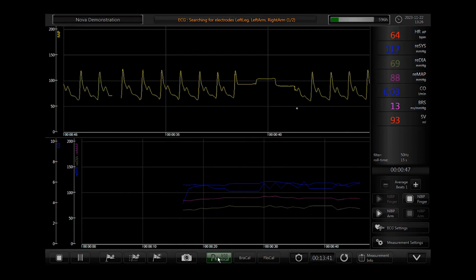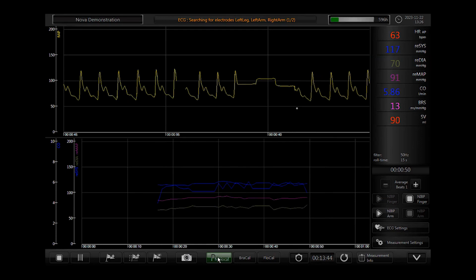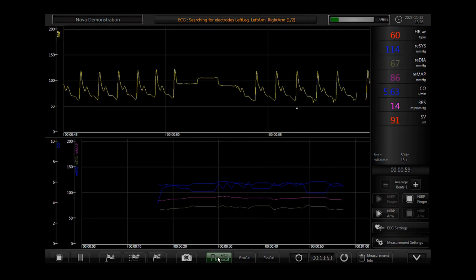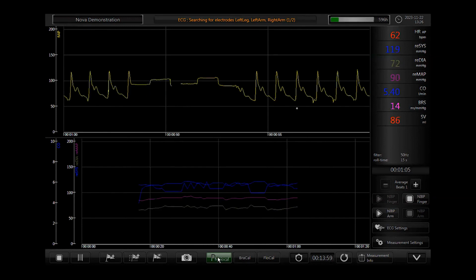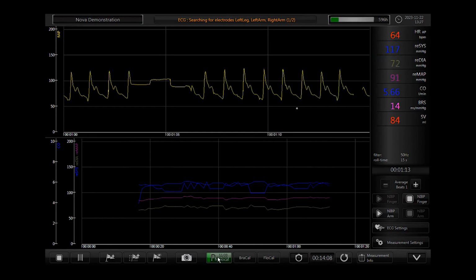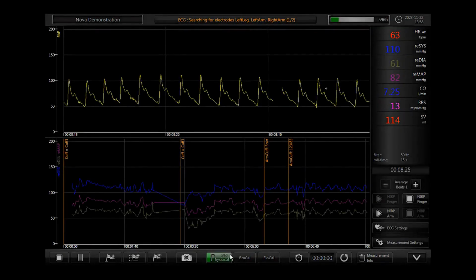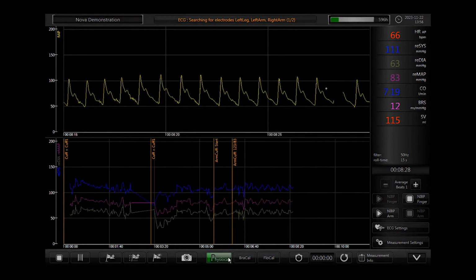It's important to note you can also turn off the PhysioCal completely if you don't want that stepwise pattern to interrupt your data. To have confidence in your recording, you'll want to record baseline data until the PhysioCal reaches 70 out of 70 beats. And as you can see now, it just increased on the right to 20 total beats, meaning it has confidence and will continue increasing until it hits 70. You can see the PhysioCal is going to roll over to 70 out of 70 beats. And that gives you confidence that the set point is maintaining an appropriate amount of pressure.